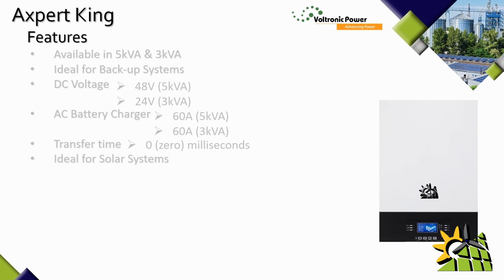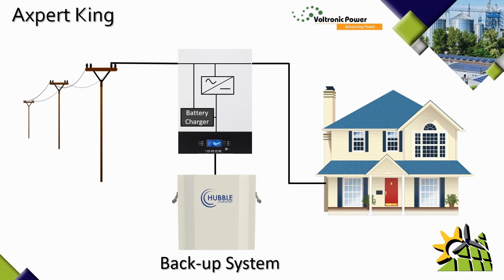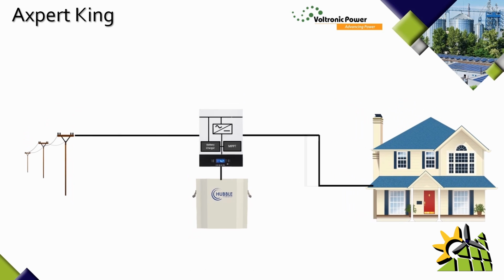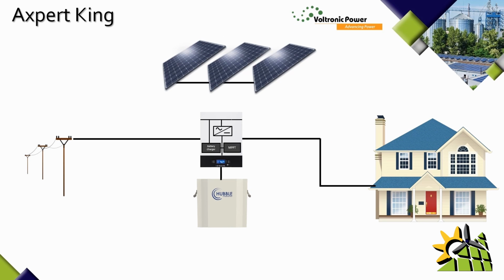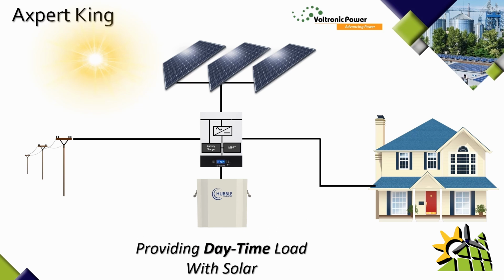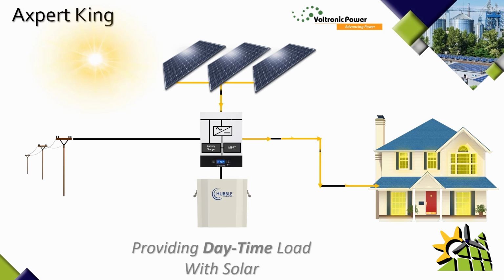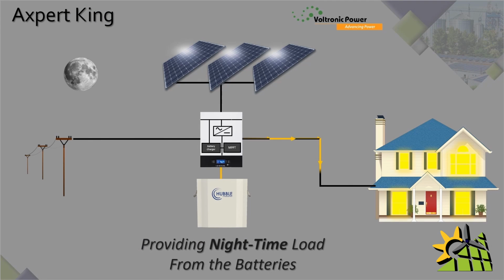This inverter is also ideal for solar systems. And the reason for that is because it's got a built-in MPPT charge controller. Now, if we had to look at a backup system where you've got your built-in battery charger, the Axpert King has also got a built-in MPPT controller, which means that you can connect solar panels to this inverter. Now, the benefit to having solar panels is that now your batteries will be charged with solar instead of the grid. You can also provide daytime load from solar, again instead of the grid, which creates a huge saving because now the grid is only needed in extreme circumstances. At night, the load will be provided from the battery.